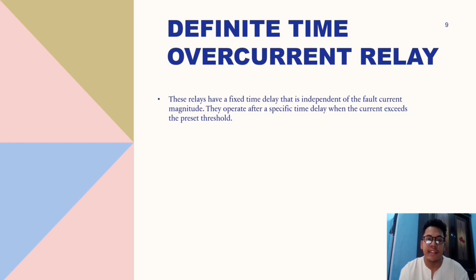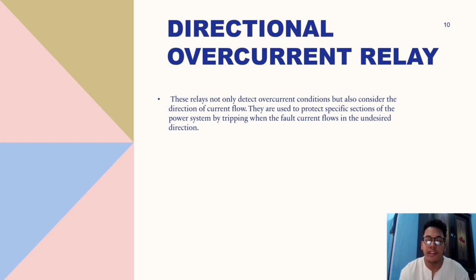Directional overcurrent relay. This relay not only detect overcurrent condition but also consider the direction of current flow. They are used to protect specific section of the power system by tripping when the fault current is in the undesired direction. Lastly is the differential overcurrent relay. These relay are used for protecting transformer and other vital equipment by comparing the current entering and leaving the equipment. They trip if there is imbalance between the current indicating a fault. So that's all for me. Thank you very much. So I will pass to my friend to explain next.